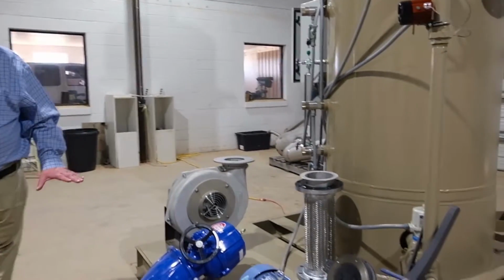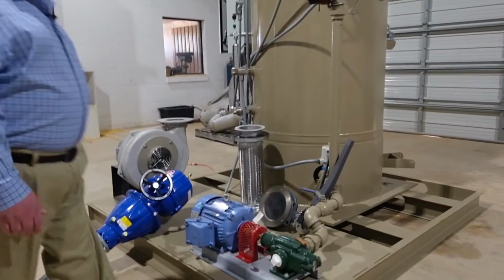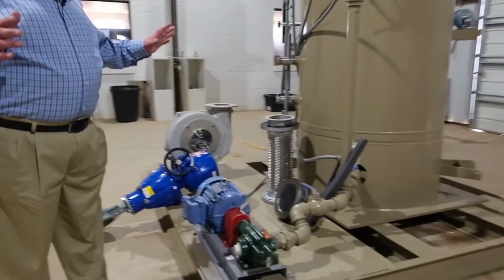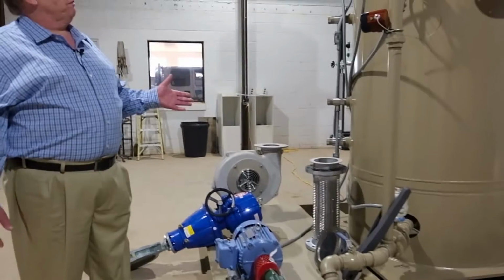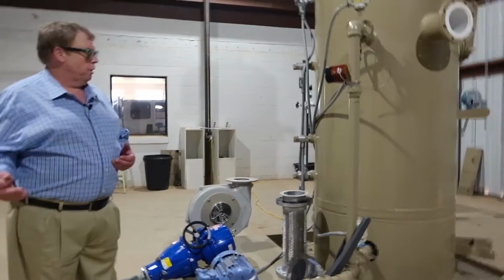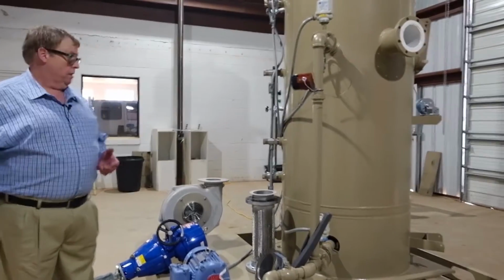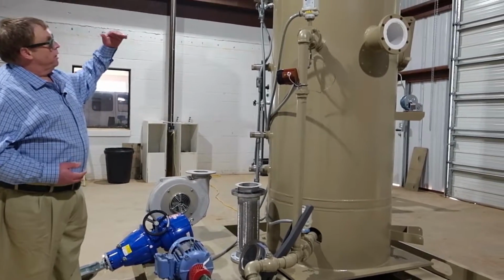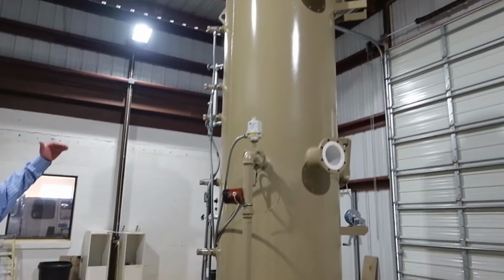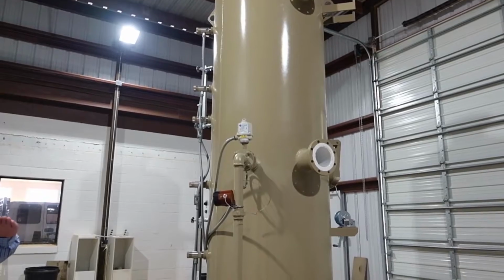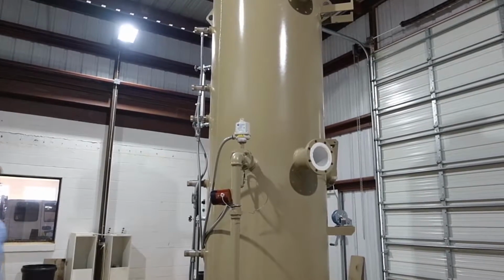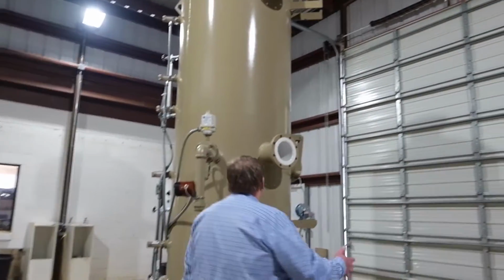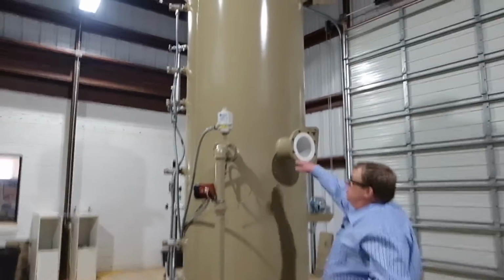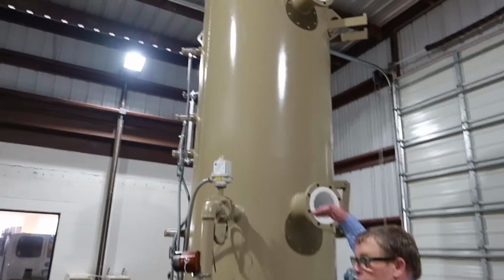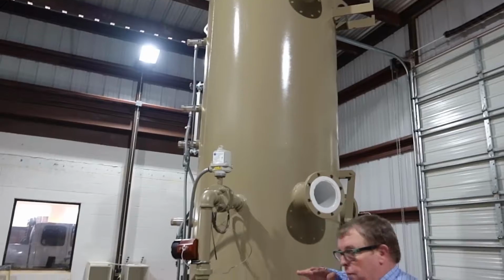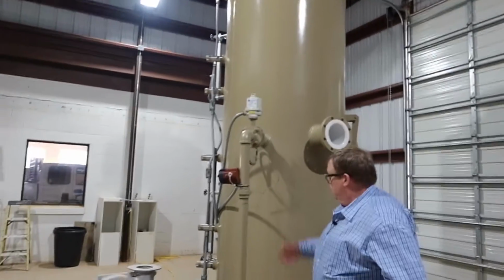Vaprox uses a gear pump to evacuate liquids. What makes a dual pressure flare is not only just handling 2 gas streams, but it's also handling 2 liquids. What Vaprox has done here is built an integral scrubber into its base so that you have 2 separate chambers, one to handle your low pressure line, which will inlet right here. Secondary is your high pressure line above it, so you have 2 separate chambers to handle that.